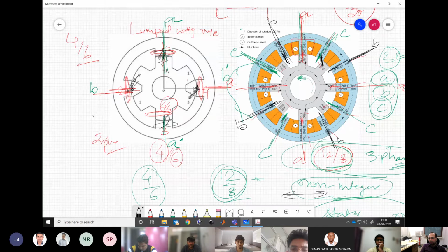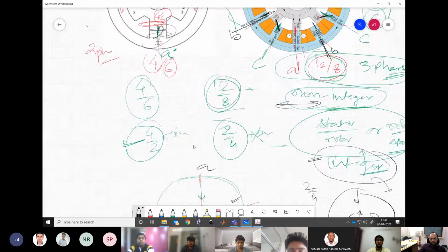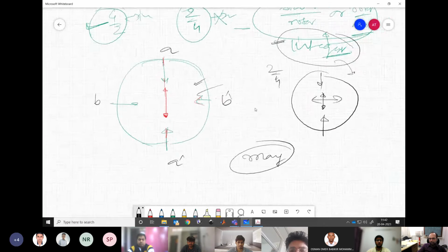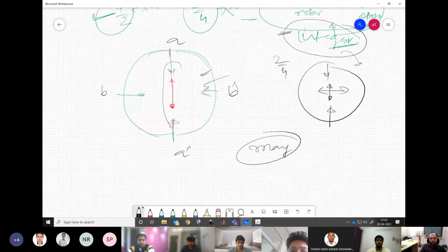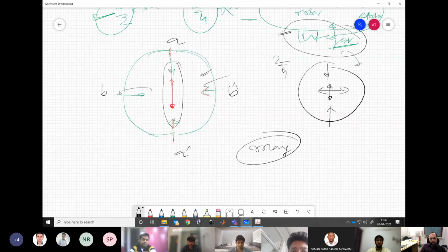Let's say this combination which I am talking about. Understanding my point? So if you excite the next phase of coil, irrespective of where the position for the first coil is, it will go and get aligned. Whereas in a combination like 4/2 or any other integer combination, you will have a tendency like this. So if it is locked out, even if you excite this B dash, nothing will happen. It is stuck in that position. Understanding my point?